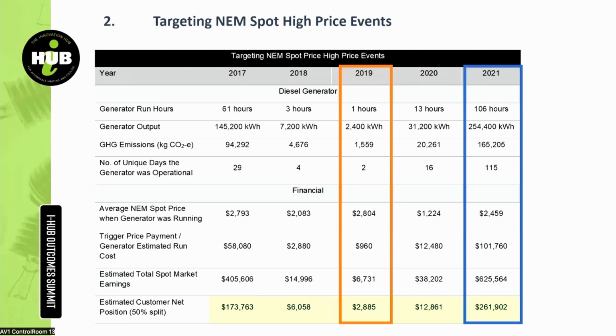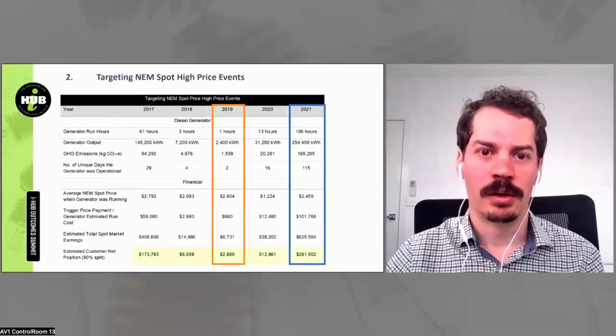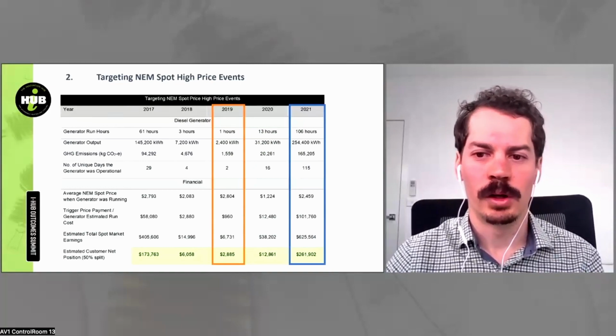And again, we can review the best year first, which was 2021 in the blue. In this year, the generator responded to spot price events above $400 per megawatt hour on 115 unique days and ran for 106 hours. During these events, the average spot price was $2,459, leading to a net customer position of approximately $262,000 after the 50% split with the retailer. However, in 2019, which was the worst year in orange there, the generator only responded to 2 unique days and ran for a total of 1 hour. This resulted in a net customer position of $2,800 after the 50% split with the retailer. So this demonstrates how volatile the spot market is, and earnings can vary significantly between years.